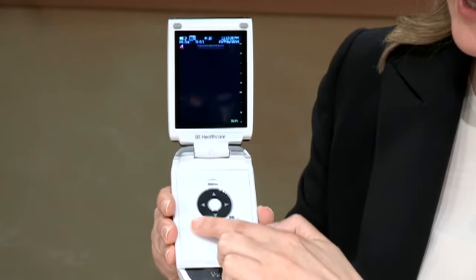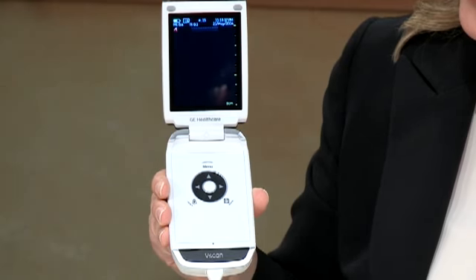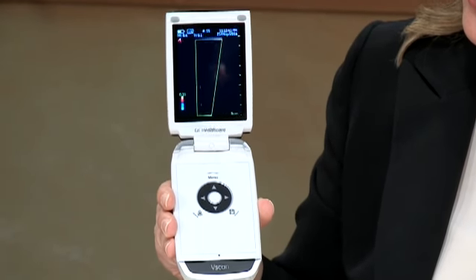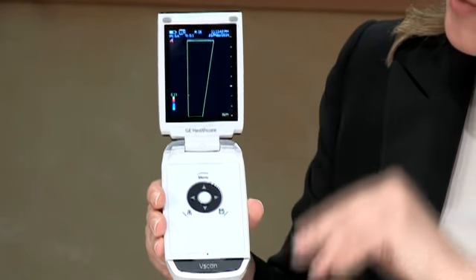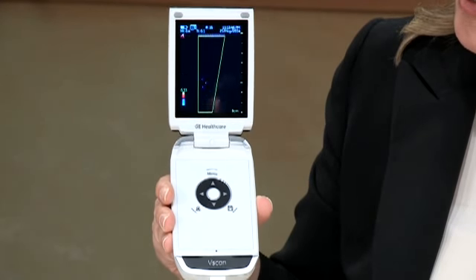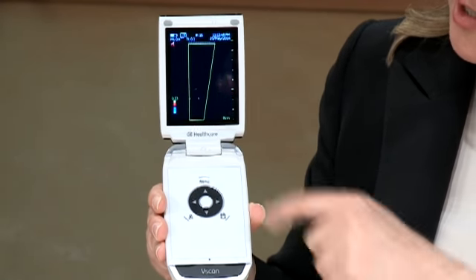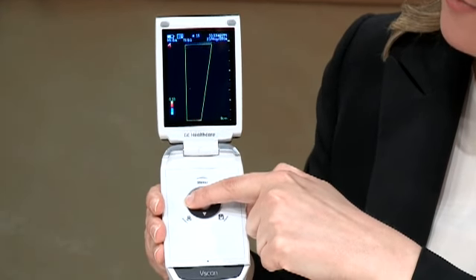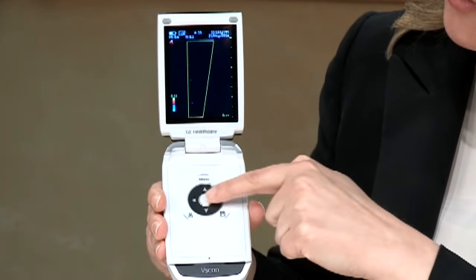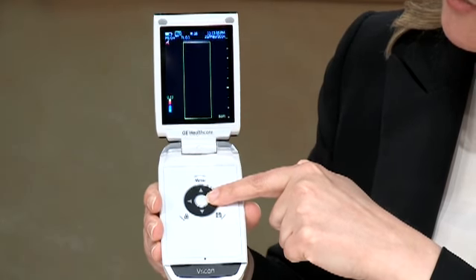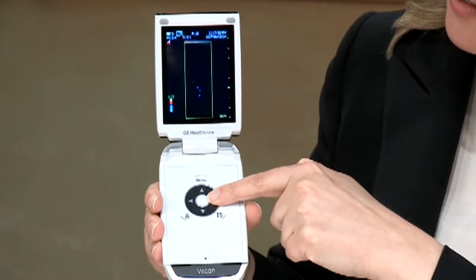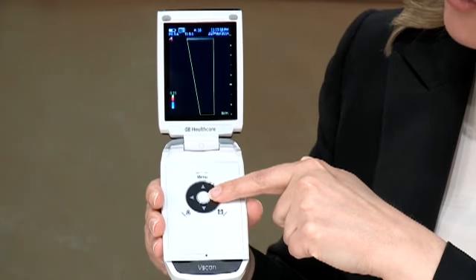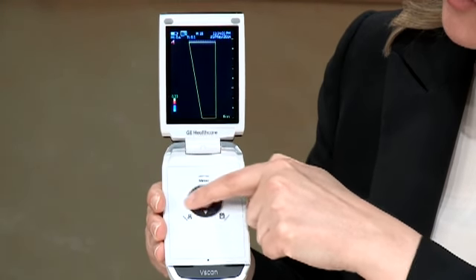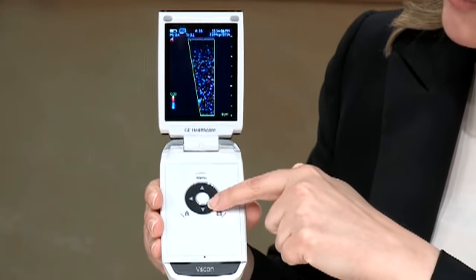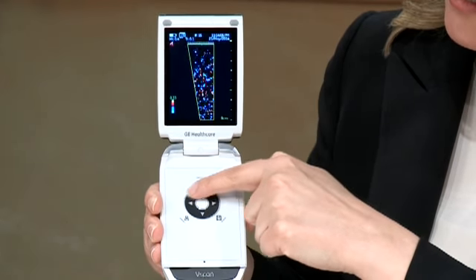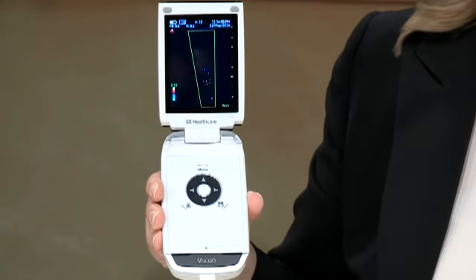Color is available. By pressing color, the color region of interest will appear. The color region of interest has been maximized to take up the entire image to reduce keystrokes. By pressing the right and left arrows, the user has the ability to steer the color box during the Vscan exam. While active in color flow, the black wheel serves as the color gain. Clockwise motion increases the color gain, counterclockwise decreases color gain.